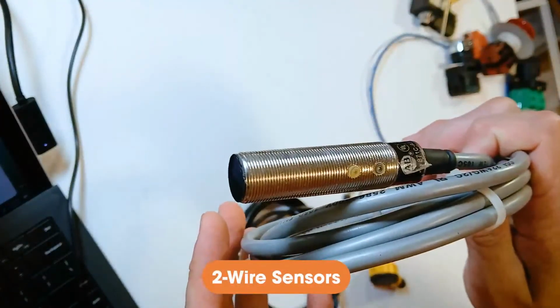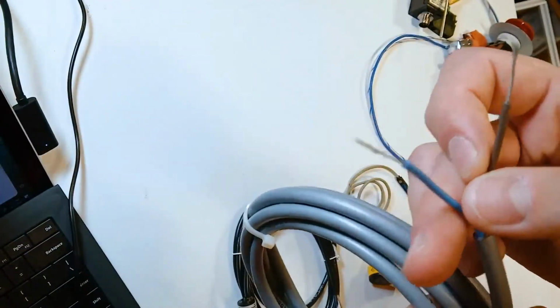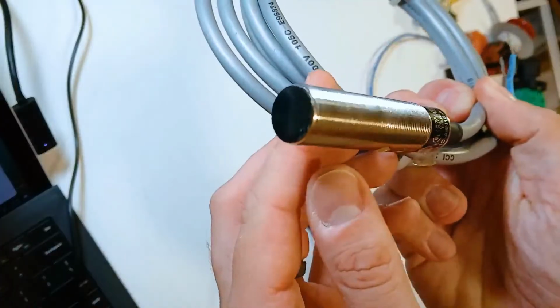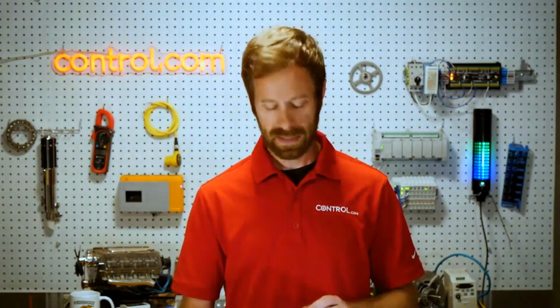These 2-wire sensors, in this case, an inductive proximity sensor, which can sense metal, provide an electrical flow between positive and negative, or in this case, as it is an AC sensor, between a live and a neutral wire, and that provides the voltage required to create an oscillation of a magnetic field in the sensor. And when the presence of ferrous metal comes into that sensor's field of vision, it changes the electrical field and turns on a switch inside that can provide that signal out to the PLC.